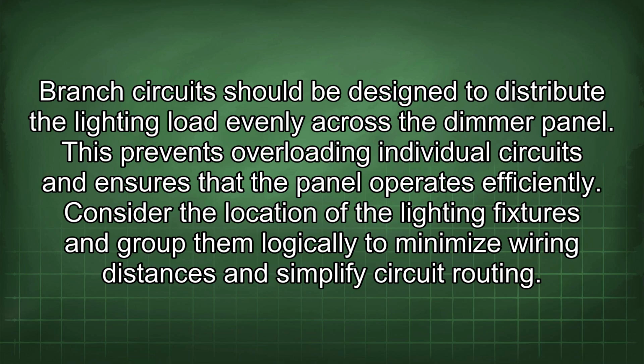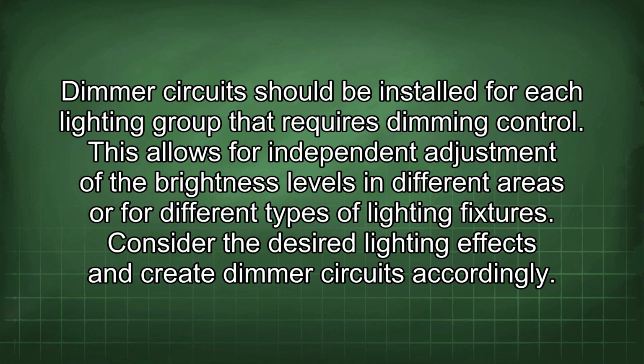Consider the location of the lighting fixtures and group them logically to minimize wiring distances and simplify circuit routing. Dimmer circuits should be installed for each lighting group that requires dimming control. This allows for independent adjustment of the brightness levels in different areas or for different types of lighting fixtures. Consider the desired lighting effects and create dimmer circuits accordingly.